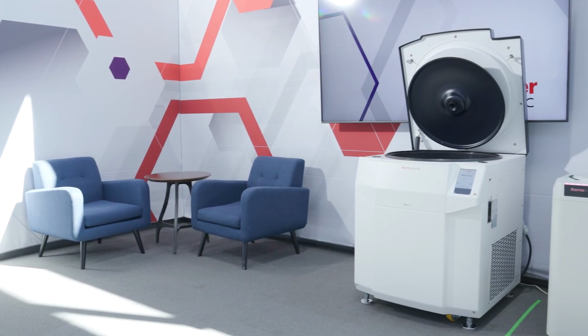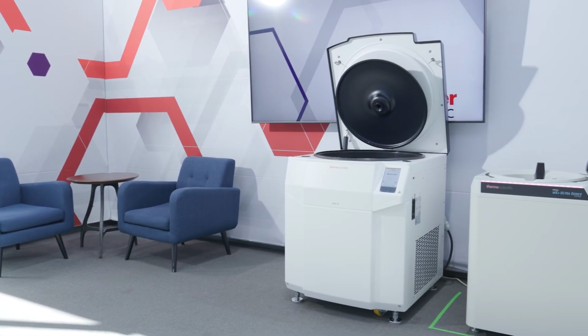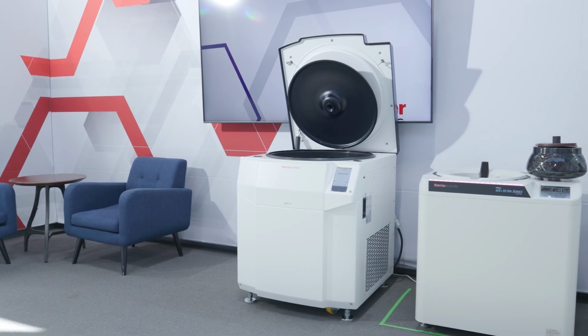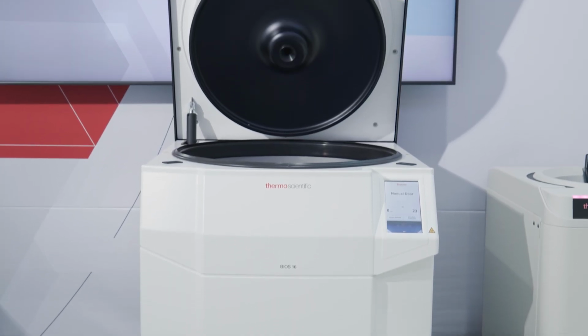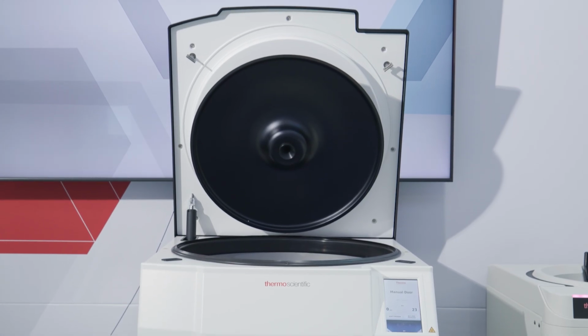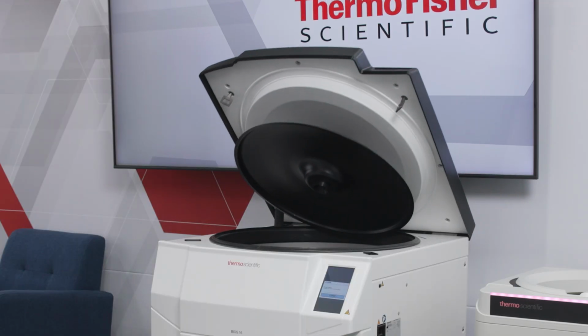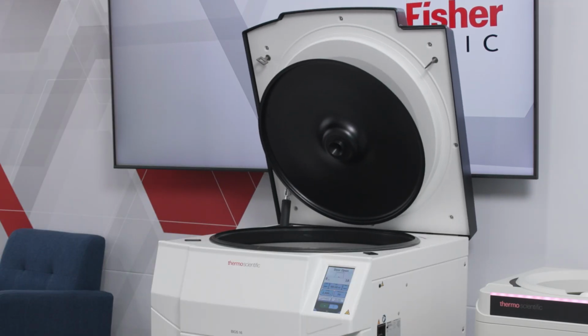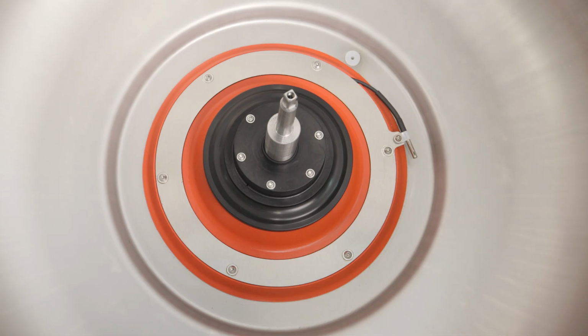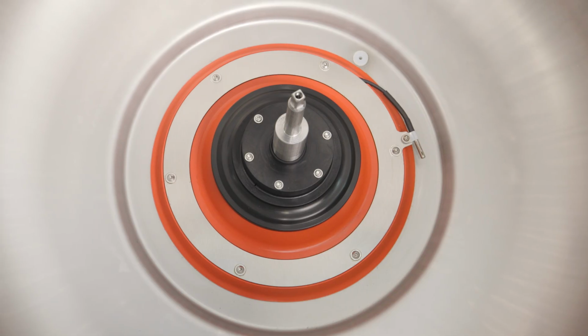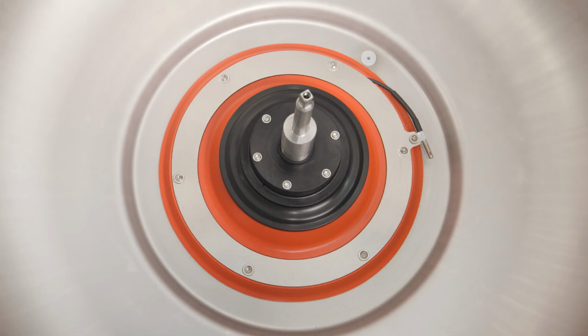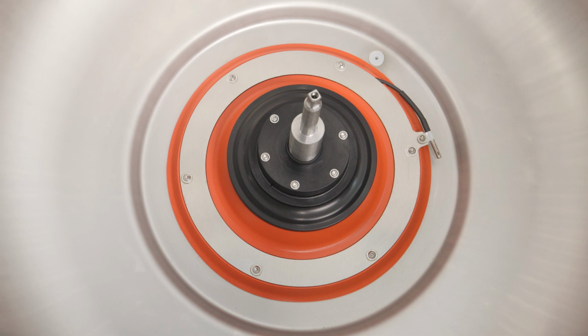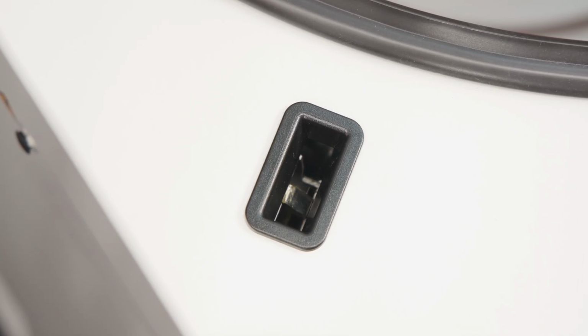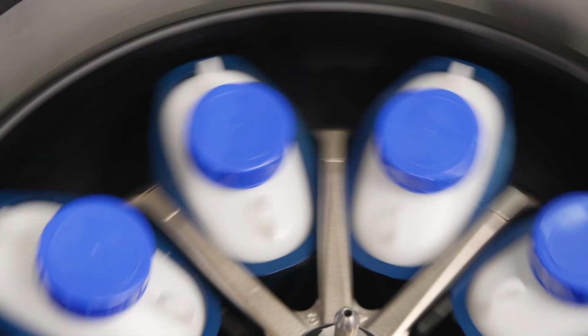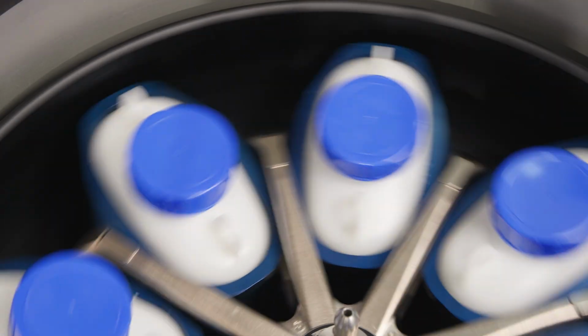In this video, we'll review how to clean and maintain the Thermo BIOS 16 high-capacity centrifuge with GreenCool technology. Please note that the drive and door lock can be damaged by liquids. Do not allow liquids, especially organic solvents, to encounter the drive shaft, drive bearings, or the centrifuge door locks. Organic solvents break down the grease in the motor bearing, which can cause the drive shaft to lock up.